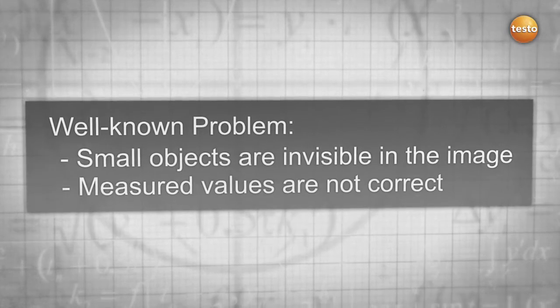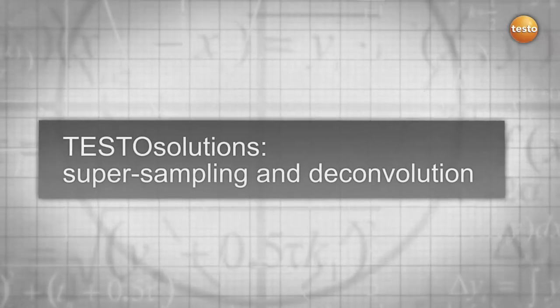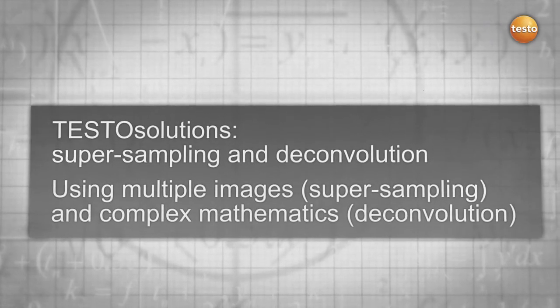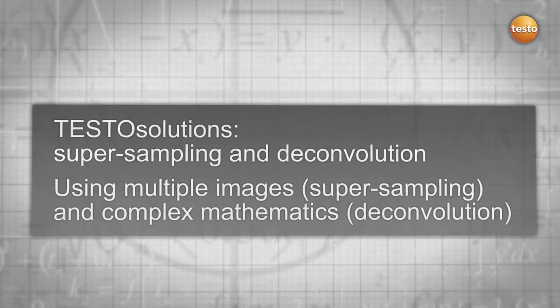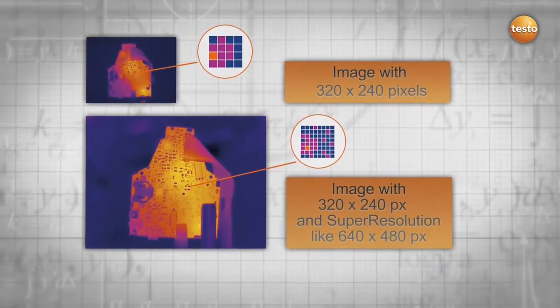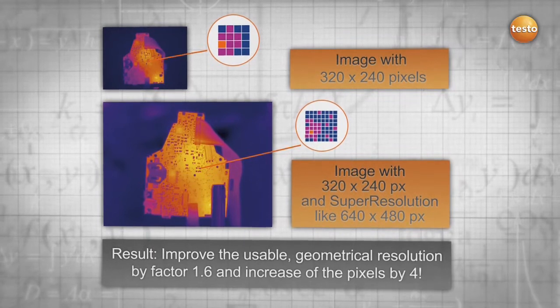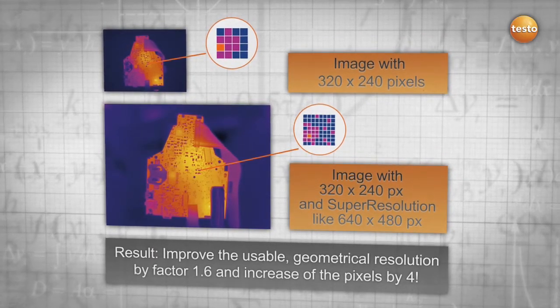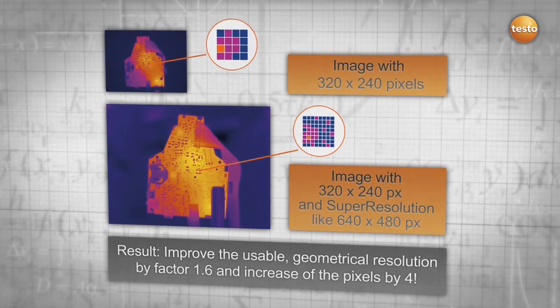By using multiple images, super sampling, and complex mathematics deconvolution, you get more information out of your thermal images. Your result: an improvement of the geometrical resolution by 1.6 and an increase in your pixels by 4 for more details and safety.